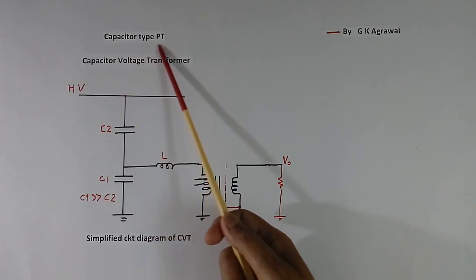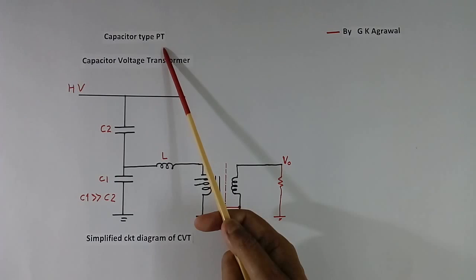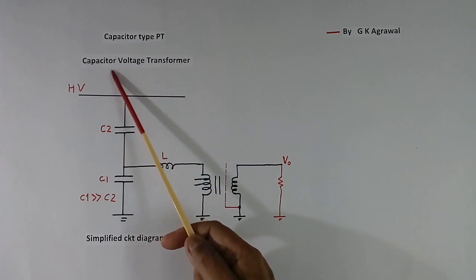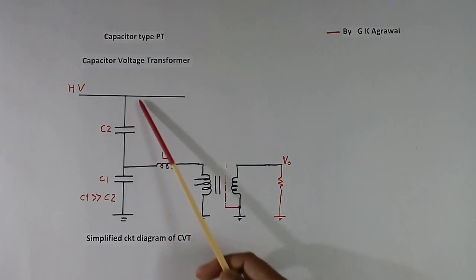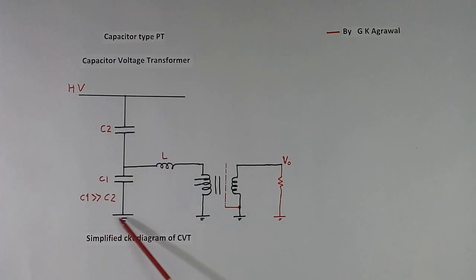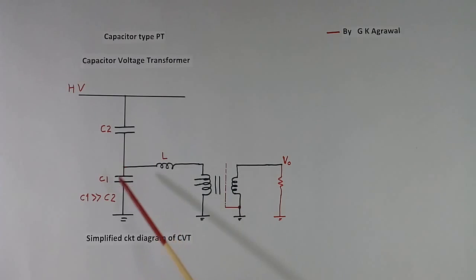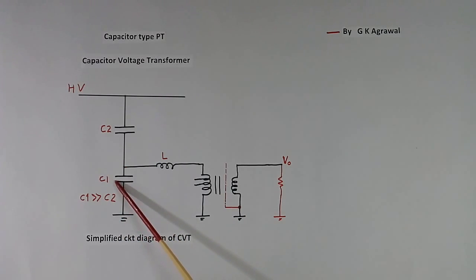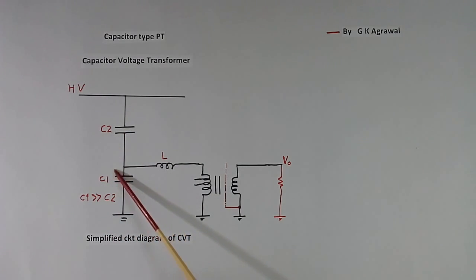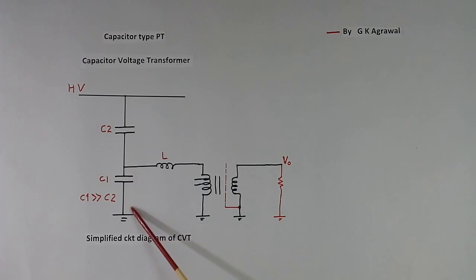This is the capacitor type PT, also called a capacitor voltage transformer (CVT). It has no high voltage winding. There are two capacitors used as a voltage divider. This type is used because the cost of this capacitor divider is lower compared to a winding-type transformer. This point is grounded. The value of C1 will be more than C2, so the impedance of C1 will be less and less voltage will appear across it.